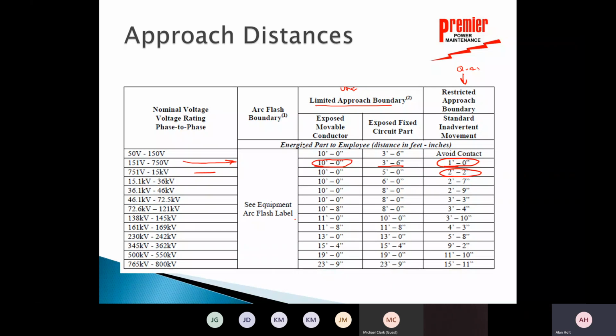Up to 138 kV, which is here, is 3 foot 10 inches. I'm telling you guys, you get above 480 volts, we want to stay 10 feet away. If we have to get closer than 10 feet, we need to huddle up and have another job safety analysis before we get any closer than that.